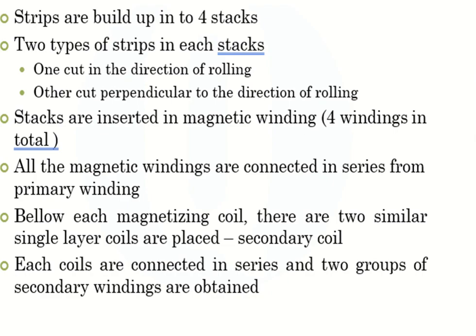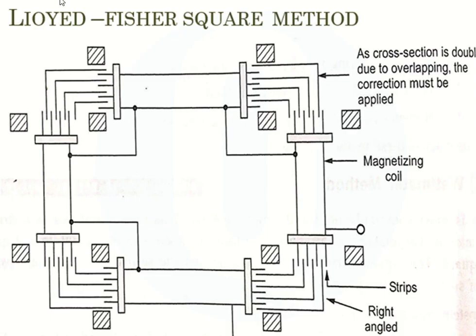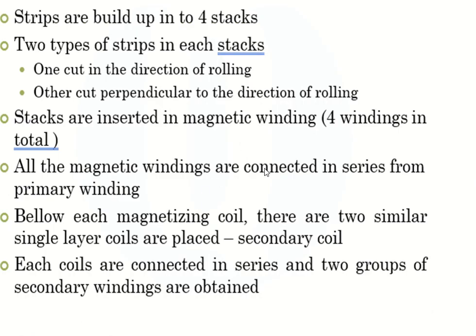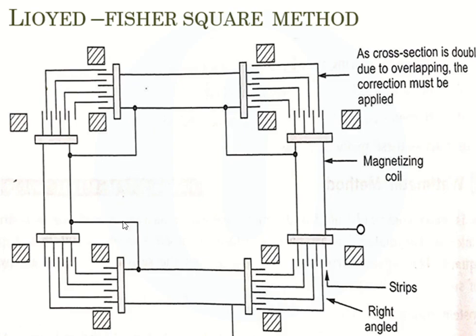The stacks are inserted in the magnetizing winding. This is the magnetizing coil — the first two layers of the coil form the magnetizing coil. All the magnetizing windings are connected in series to form the primary winding.